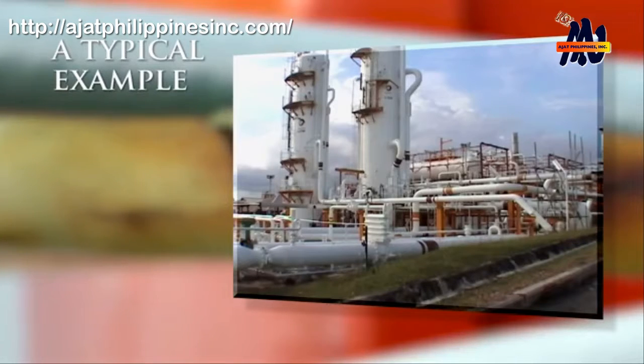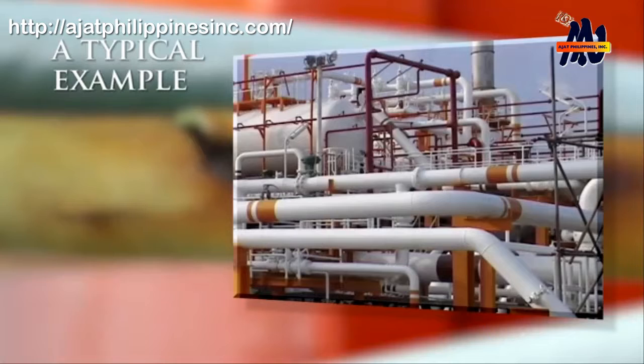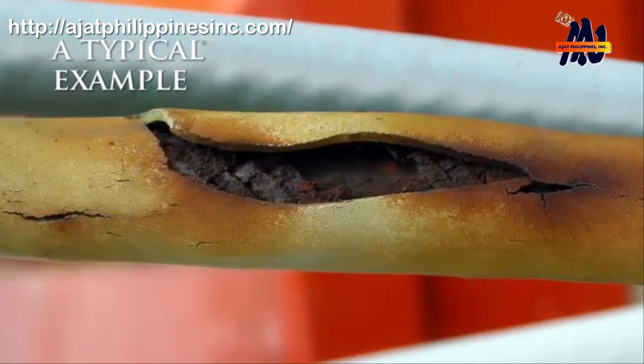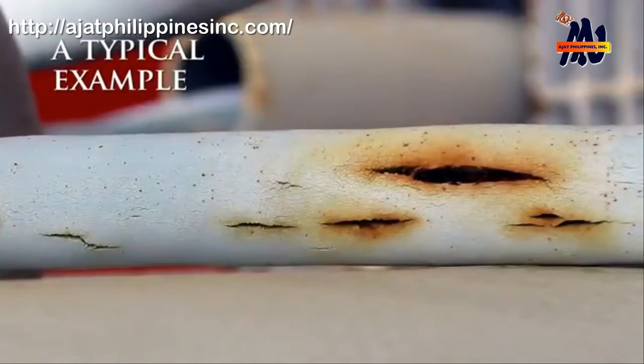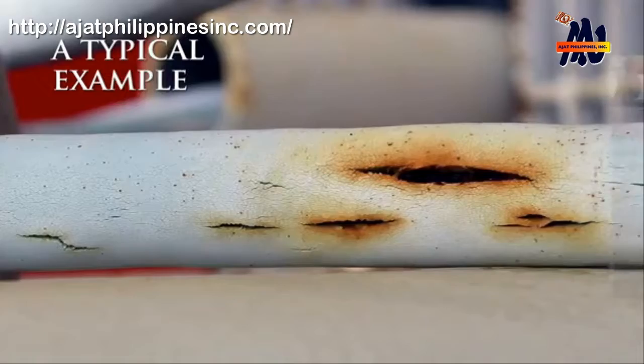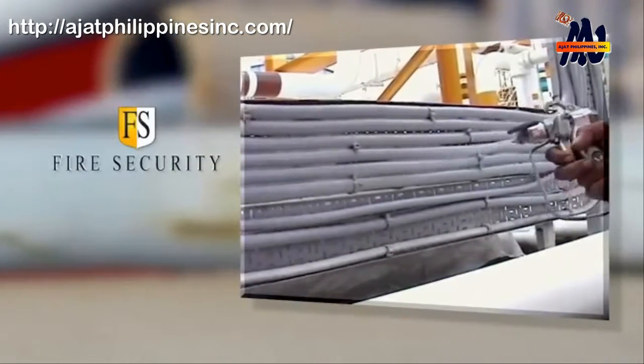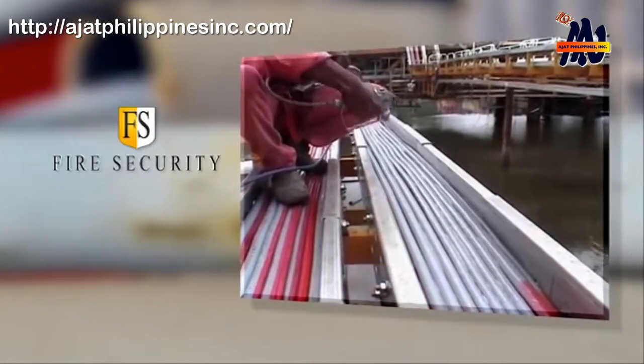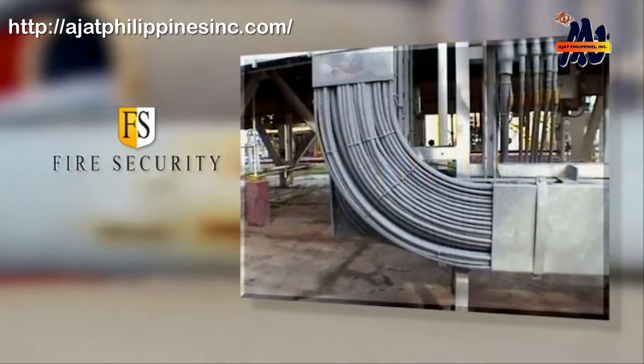A typical example is what Fire Security have done for the Senipa terminal in Indonesia for the oil company Total. The outer sheath of the cables was damaged, mainly by UV, and had a lot of cracks, which led to short-circuiting and sometimes loss of production. Fire Security repaired all the cracks and coated the cables without any stop in the production. We have extended the lifetime of the cables and at the same time made the cable fire resistant.